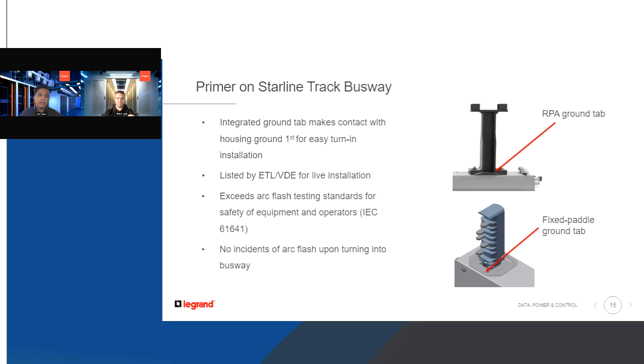Before I get into that, I will reiterate that Starline Track Busway is designed for live insertion. We establish ground first and last when you install a plugin. On top of that, we did voluntary testing, IEC 61641, where you intentionally set off an arc and see how your equipment behaves. Our equipment passed and exceeded that standard. So safe to say, busway in itself is designed for live insertion. What we are seeing though, with this increasing power demand, is some customers shutting down the busway to add circuits, and in response, we're hearing these concerns.